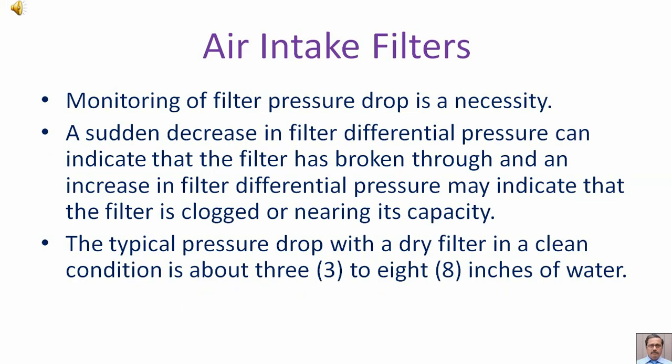Monitoring of filter pressure drop is a necessity. A sudden decrease in filter differential pressure can indicate that the filter has broken through, and an increase in filter differential pressure may indicate that the filter is clogged or nearing its capacity. The typical pressure drop with a dry filter in a clean condition is about 3 to 8 inches of water.